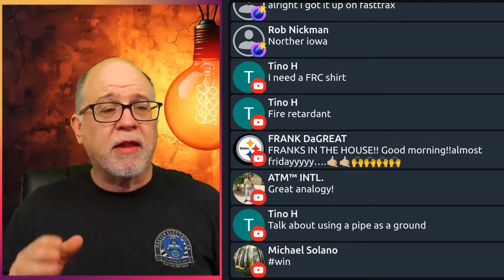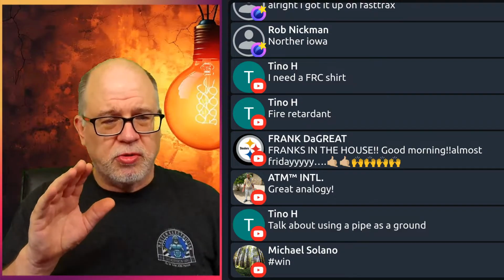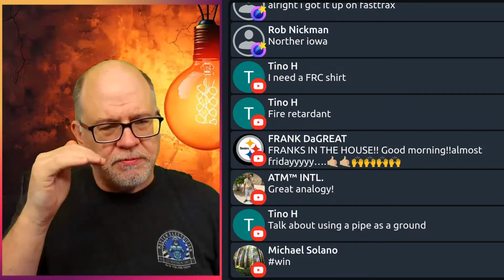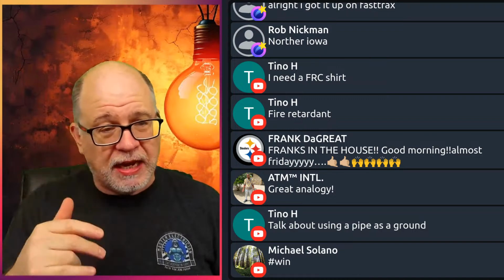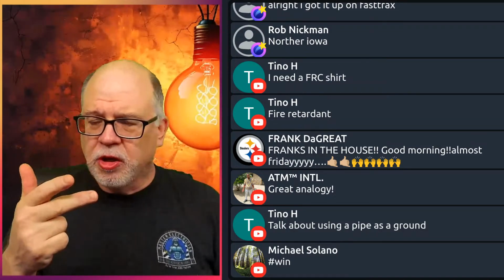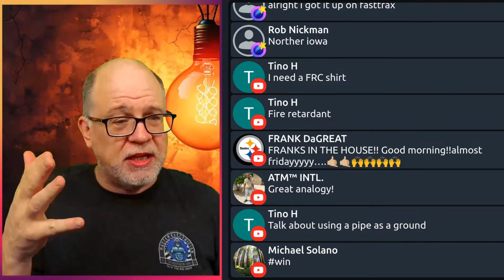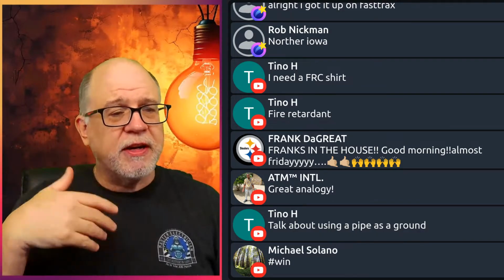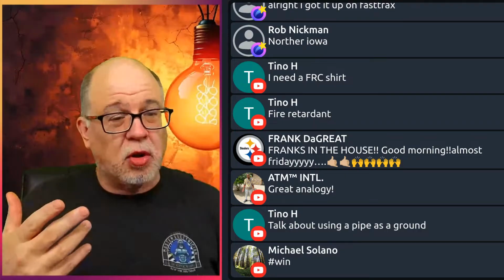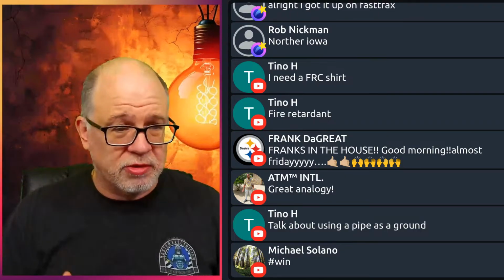Usually the most common would be ground rods, concrete encased electrodes. And all of these, by the way, are in 250.52, (A)(1), 2, 3, 4, 5. You get to see all of them, the different types like plates, rods, pipes, rings, the in-ground steel, things like that. Different types of electrodes. Even have the chemical type that you can get. Okay. Problem with those is that you have to replenish those, that type of thing. Okay. So anyway, that's the grounding electrode system.